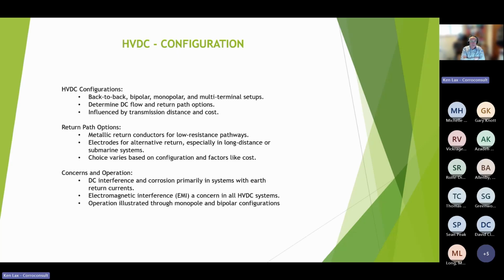That's not good for the pipelines, because a system designed to be bipolar, with two cables, produces much less interference. If we do our risk assessment on the basis that it's a bipolar system, we have to take account of when it's running in monopolar mode, because it can run that way. We also have to take account of which direction the current is flowing, because that can affect the risks of interference. So the return path options are pretty straightforward: it's either a hard wire or the earth.